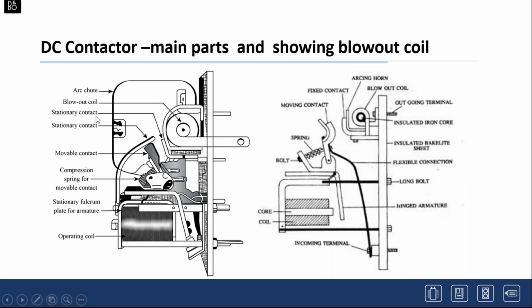Now, I mentioned blowout coils. And I think that this is a good way to illustrate the makeup of a DC contactor. There's a lot of detail here, and I'll just walk through. This illustration is a back-connected version, but you have the arc chute, the blowout coil, the stationary and movable contacts, the compression spring, then you have the operating coil and a hinged armature here that operates the movable contacts. In this device, these would be the mounting screws for a back connected device. And here you have your power buses.